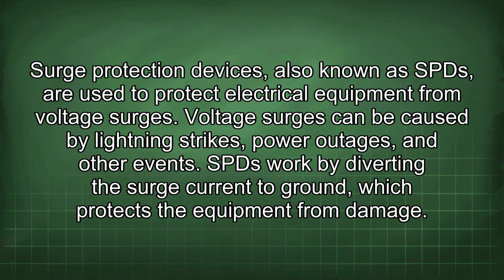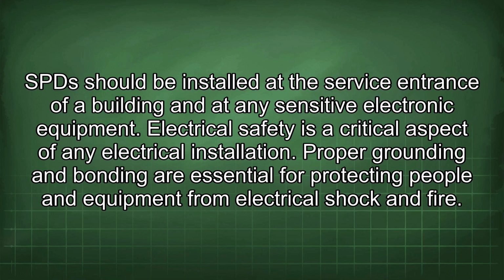Surge protection devices, also known as SPD, are used to protect electrical equipment from voltage surges. Voltage surges can be caused by lightning strikes, power outages, and other events. SPD work by diverting the surge current to ground, which protects the equipment from damage. SPD should be installed at the service entrance of a building and at any sensitive electronic equipment. Electrical safety is a critical aspect of any electrical installation. Proper grounding and bonding are essential for protecting people and equipment from electrical shock and fire.